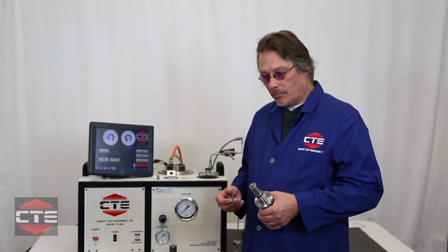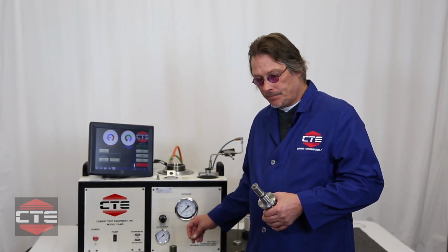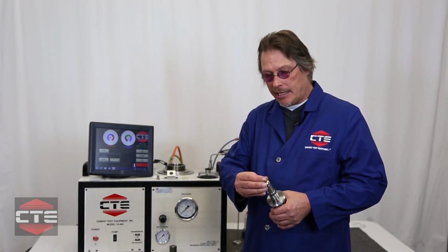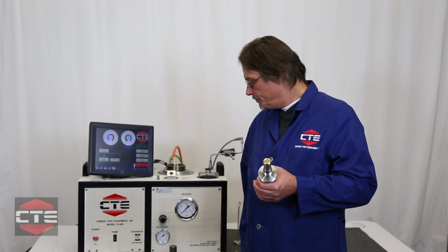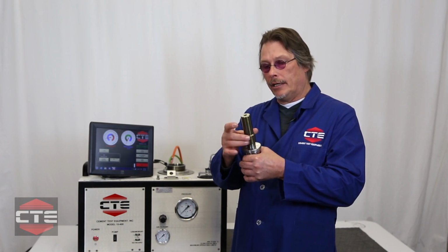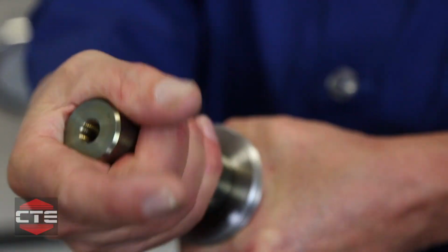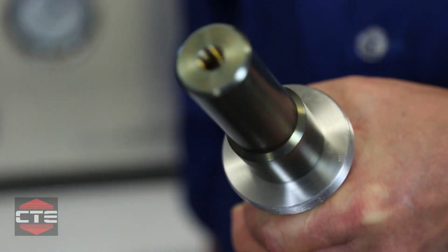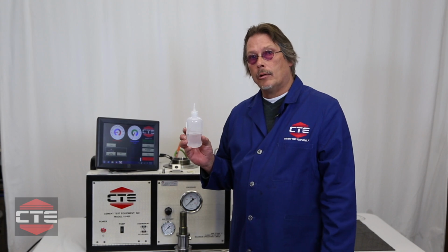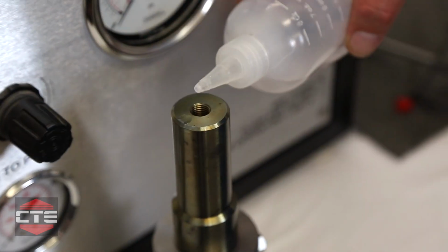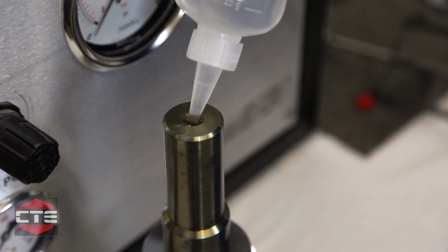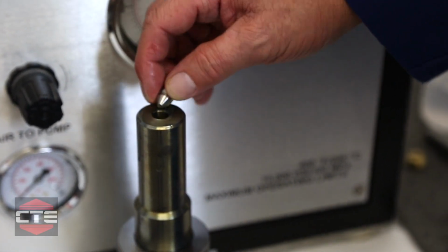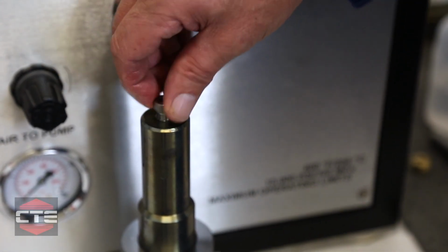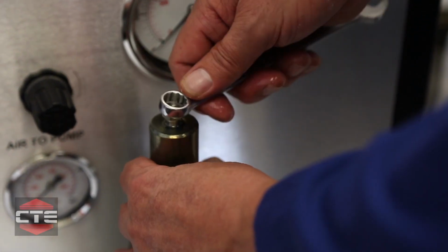Okay, now we're ready to reinstall our mag drive housing, starting with your upper bearing retainer. It slides over the bearing, and then we're going to screw our housing onto the plug, making sure it bottoms out all the way. It will be a little tight with the new poly pack, but that's what you want to hold the oil inside of it. What I have here is just your regular mineral oil that you use to operate the instrument. I'm going to simply fill the upper mag housing with oil and reinstall your medium pressure plug into the top of your mag drive housing and tighten with a 1/2 inch wrench.